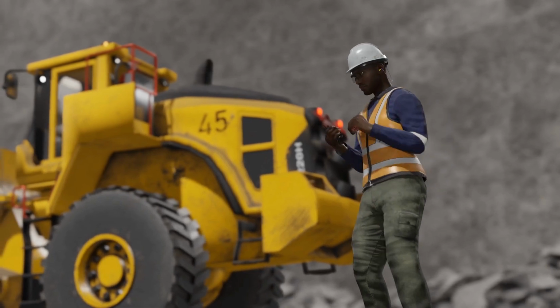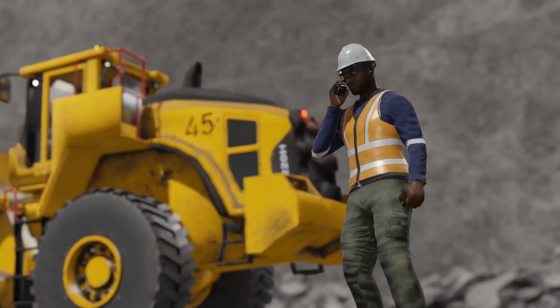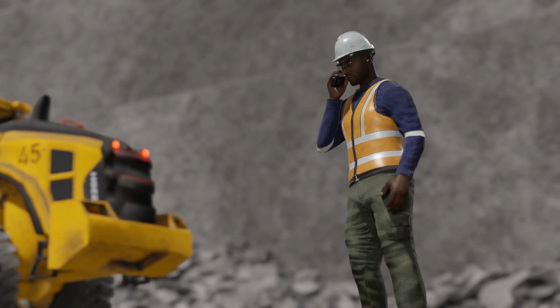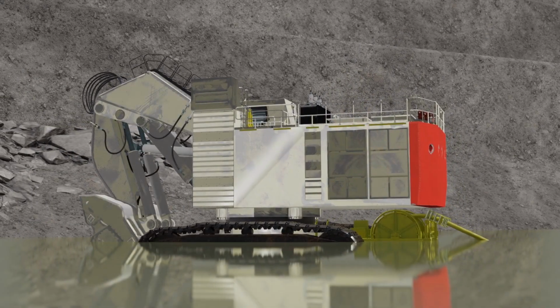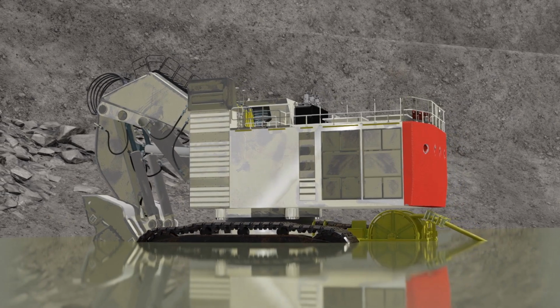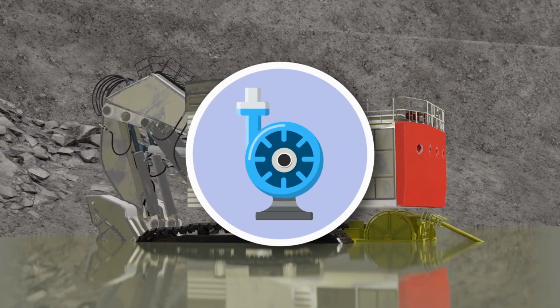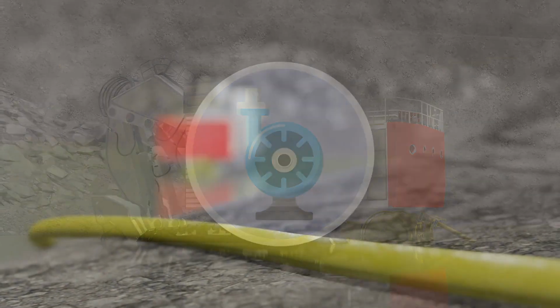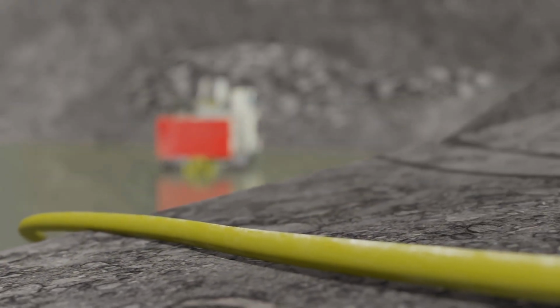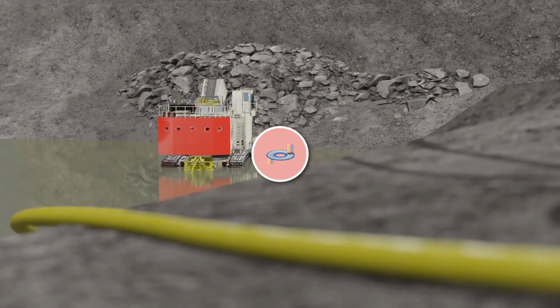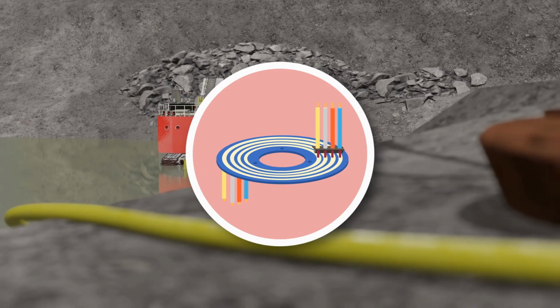The pit supervisor requested cable reelers to bring two replacement feed cables to first supply power to FS-115 so that it could be moved out of the loading area to allow the team to start work on the sump pump. After installing the two feed cables, FS-115 was powered. However, the slip rings flashed due to flooding.